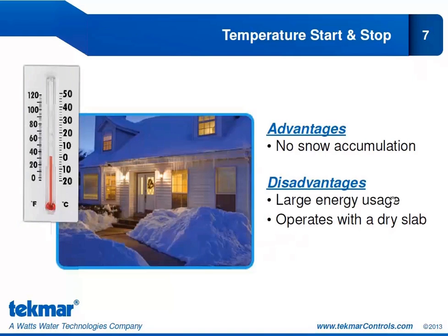The disadvantage is that this method uses a lot of energy. So it's on for the entire snowmelt season, and typically it only snows for 10% of the days where we're below freezing. So for the other 90% of the time, we are just wasting energy.